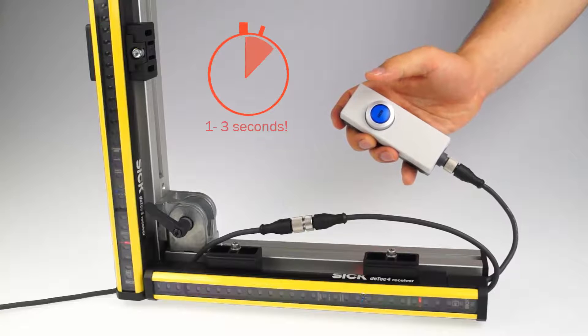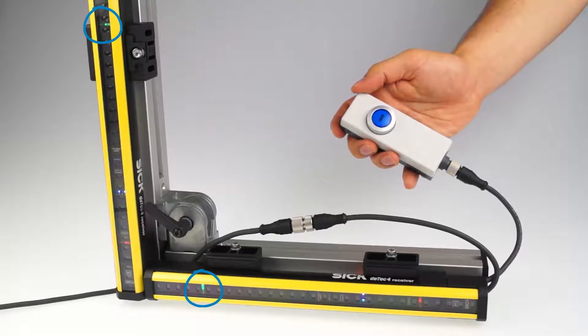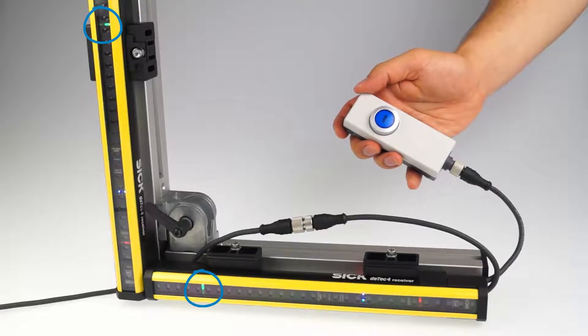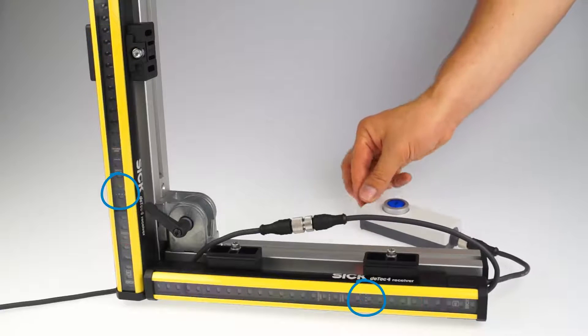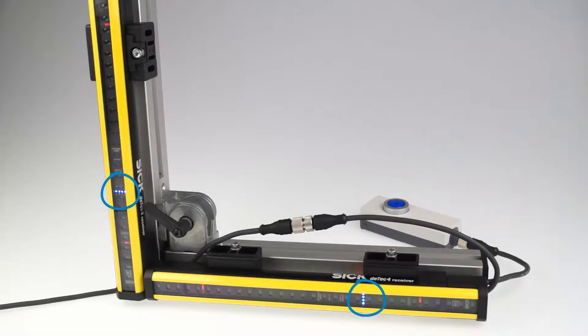To signal that the configuration has been successful, the device's field LEDs flash green. The blue alignment LED 4 also flashes to signal that the restart interlock is configured now. After another power cycle, the system starts up in the reset required state.